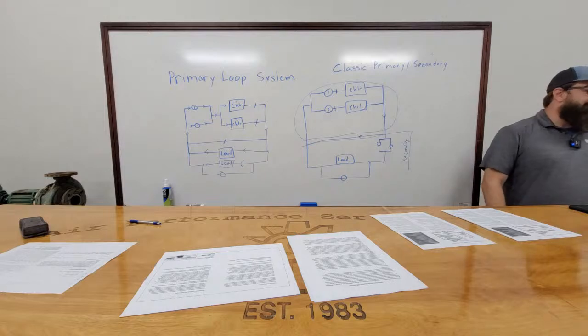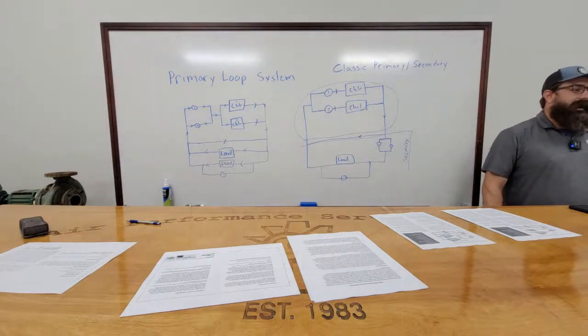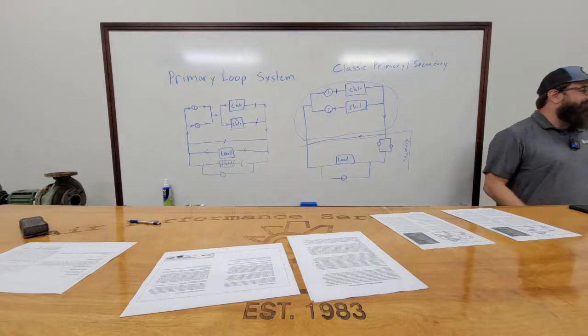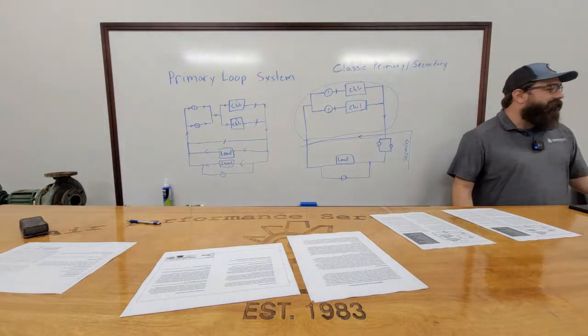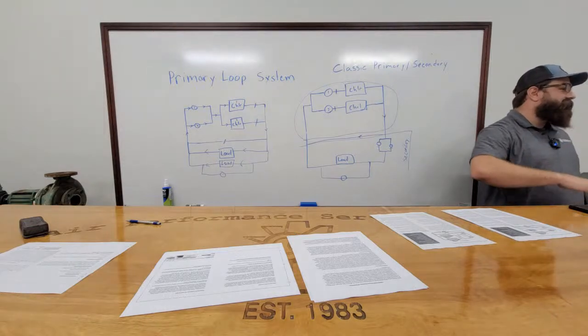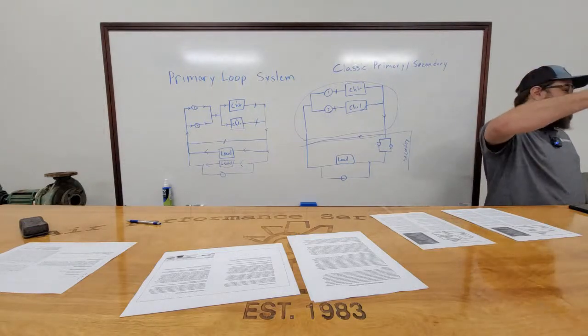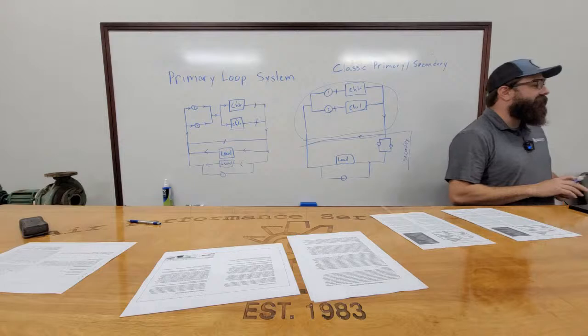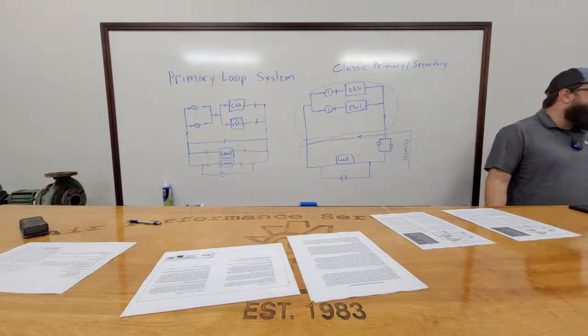So we did a school a couple years back that had a freaking bypass valve up at the top of the roof, like just a big NEMA 4 Belimo valve just sitting on the roof. We're like, what is this thing for? Then once we started looking at the building, we found out every single air handler had two-way valves. So they had a bypass valve up on the top that would open and close to maintain that differential if the pumps couldn't slow down enough.